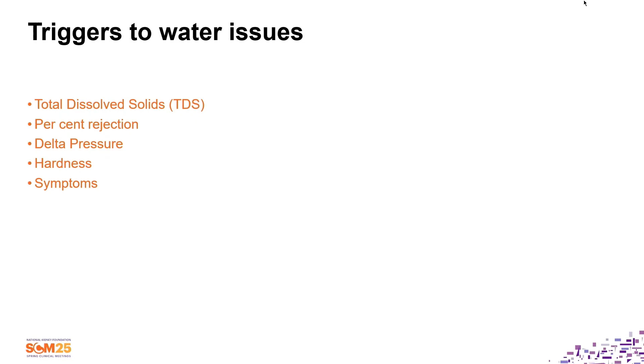So if you have 5 patients at the farthest point of the RO system having similar symptoms, is it water? There are a lot of other things that we use commonly with each treatment, with each patient. So if it's the farthest point, I would not suspect the water. I would suspect something else that's commonly used for each patient. So yeah, water's going to be a domino effect. It's logical. Okay. So in that scenario, with symptoms, know where your first station is. And believe it or not, CMS actually looks for that. During your survey, they look for, do you have a diagram of your flow system?